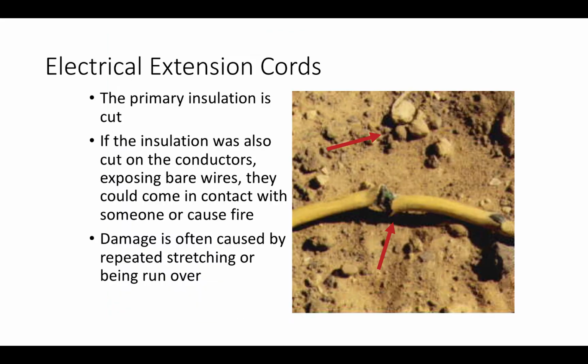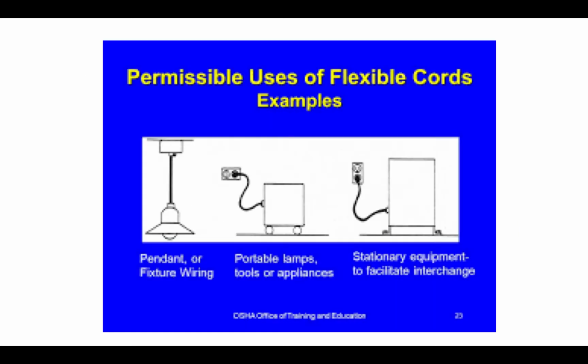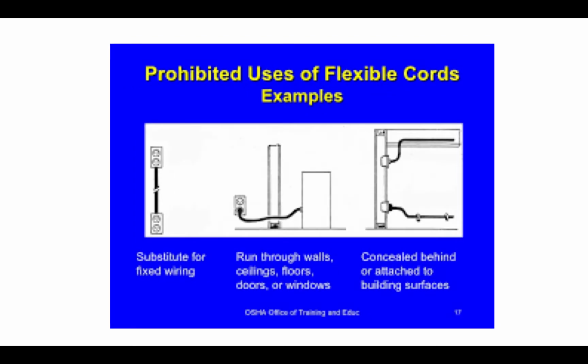Electrical extension cords cannot be used if the primary insulation is cut. If the insulation was also cut on conductors exposing bare wires, they could come in contact with someone or cause fire. Damage is often caused by repeated stretching or being run over. There are permissible uses of extension cords. Okay, you can use them for fixture wiring, portable lamps, tools, or appliances, or stationary equipment to facilitate interchange. Prohibited uses of flexible cords: substitute for fixed wiring, running through walls, ceilings, floors, or windows, concealed behind or attached to building structures. They cannot be permanent installations.